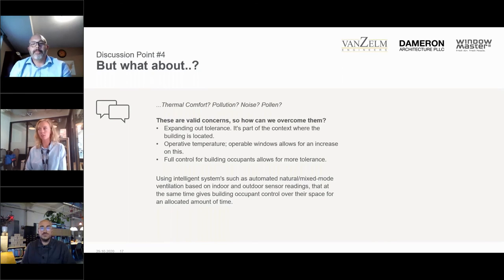To round this off, from our experience it's also about discussing what kind of system you're specifying for natural ventilation or mixed mode in a building. There are technologies on the market now that are sensor based and intelligent, using indoor climate measures like CO2, temperature, and relative humidity, but also the exterior environment. In our natural ventilation systems, we always put a weather station that reads temperature, relative humidity, wind speed, and wind direction. So thinking about how the system is designed and what kind you use is important if you want intelligent systems in a project. Thank you both for your input.